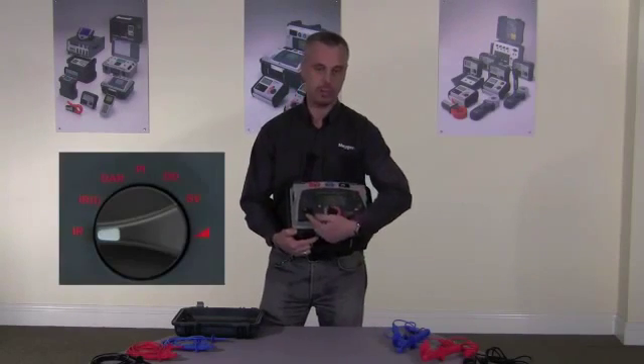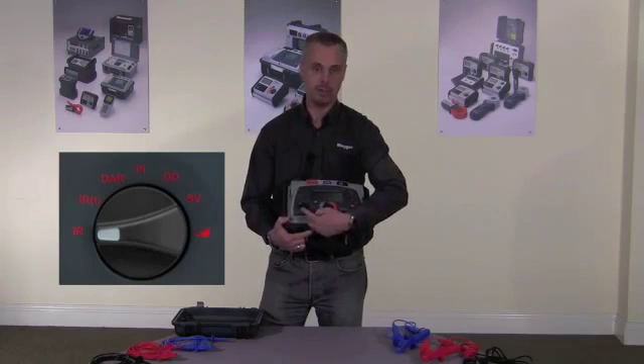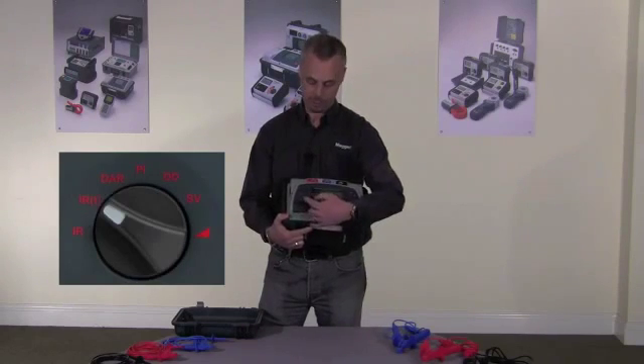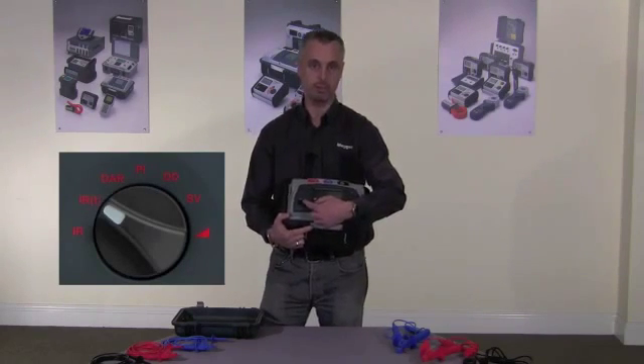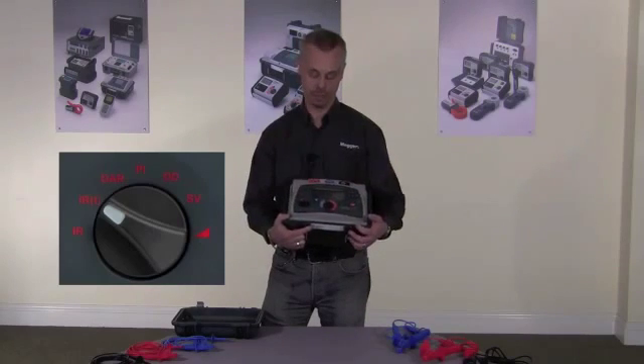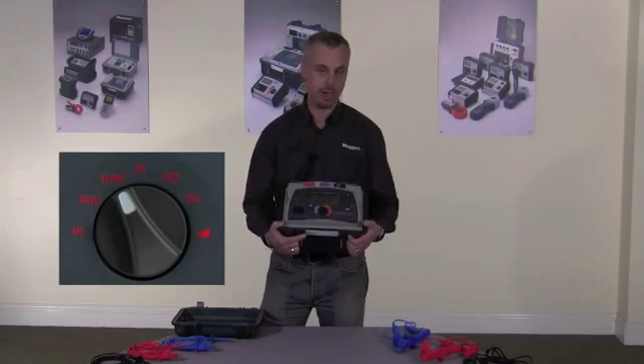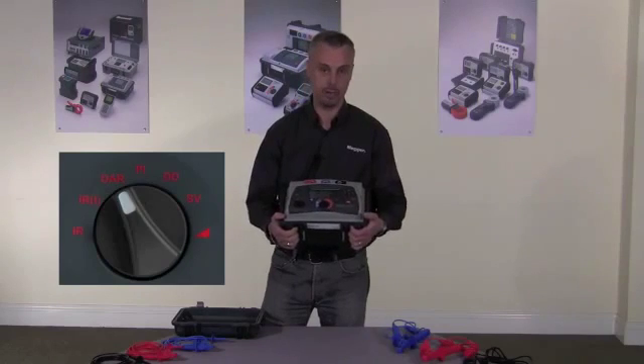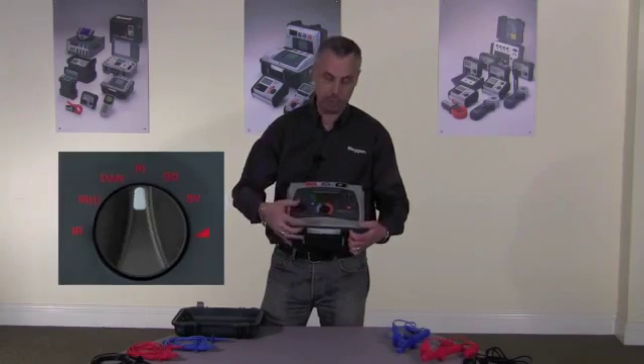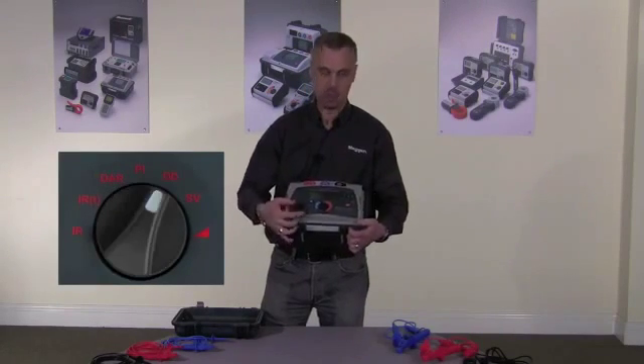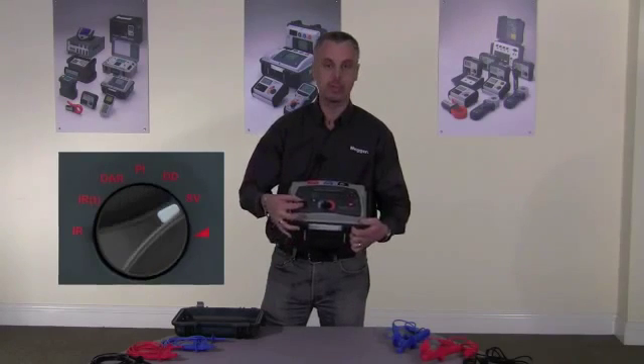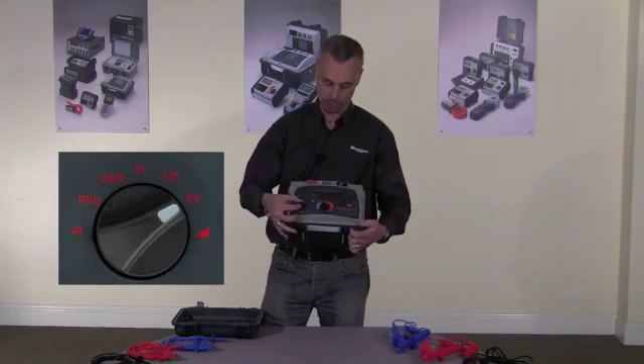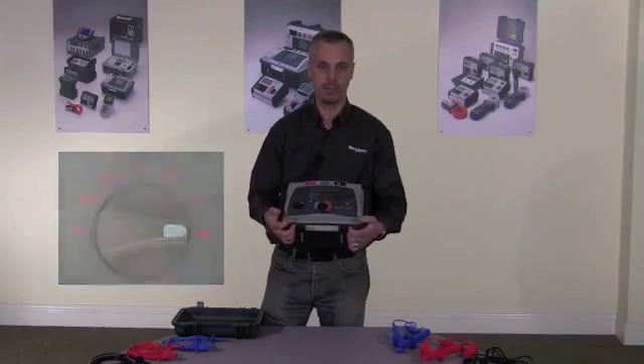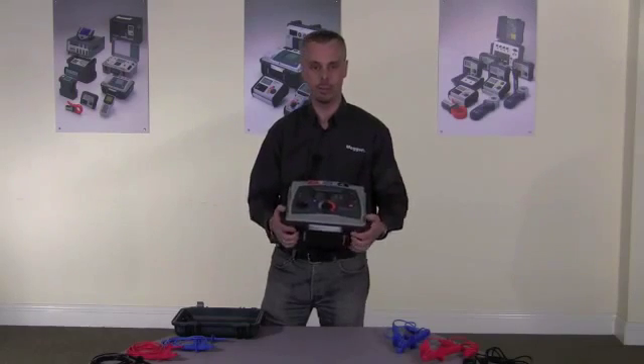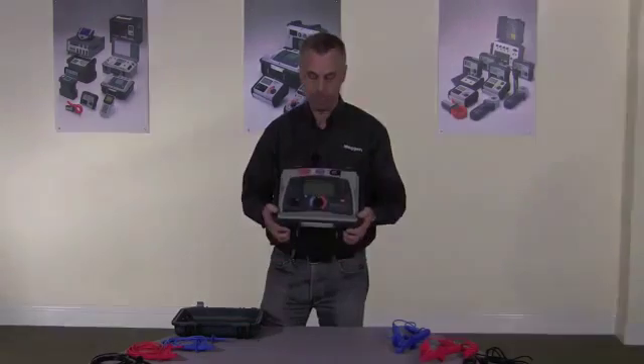On the mode selection switch here we have an IR test, insulation resistance. There's a timed IR test. This will stop automatically at the time you set. There's the DAR, which is dielectric absorption ratio, the polarization index test, dielectric discharge test, step voltage test, and finally the ramp test. So it's fully diagnostic. All the tests you require are on the product.